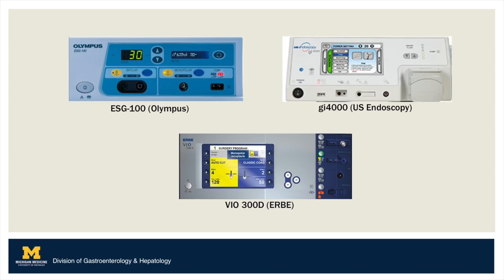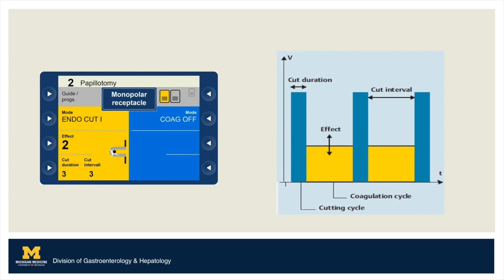For the sake of specificity, we will briefly review settings on the ERBE VIO 300D, which is a generator we carry in our units. On the left we show a representative example of a screen on the ERBE generator, here showing settings for a papillotomy. Endocut I is the name for the blended cut used with straight wire devices like a sphincterotome. Settings available to adjust include effect, duration, and interval.